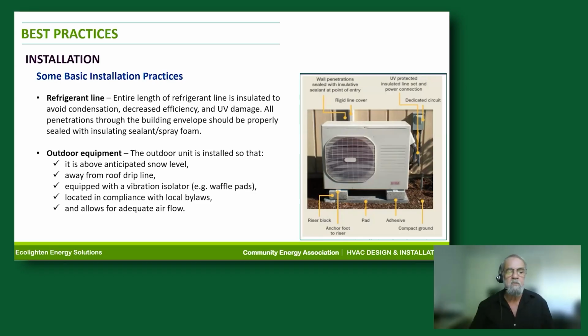You want it away from drip lines, away from roof overhangs, for example. This is another thing we don't see often enough, and we're very strict in our designs and our expectations that it exists: vibration isolation. That equipment's got a compressor, fan in it, among other things. It's going to move, even if you can't see it moving. It's always moving when it's running. What we want to ensure is that the amount of movement, the degree of movement, doesn't impact its internal circuits and components, so we want some isolation. Plus, we don't want the potential movement on a hard surface to amplify any potential noise.